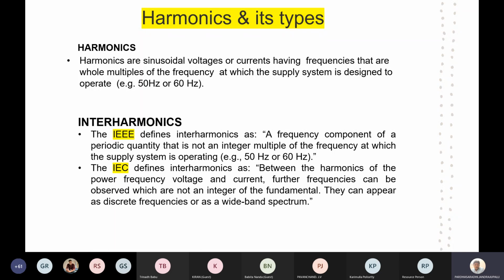There are interharmonics also present in the system. Nowadays, these interharmonics are causing various problems in the power system. So what are interharmonics? The IEEE defines interharmonics as a frequency component of a periodic quantity that is not an integer multiple of the frequency at which the supply system is operating. Whereas IEC defines that between the harmonics of the power frequency voltage and current, further frequencies can be observed which are not an integer of the fundamental. They can appear as discrete frequencies or as a wide band spectrum.